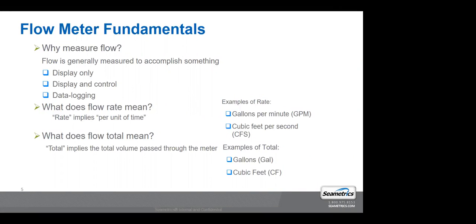Why do we measure it? We're accomplishing something. Either, like I just touched on, the totalized information, we're either displaying that data and we need to control something, control the pump, control something at that site, or we're data logging. How much water are we flowing through a given period of time? Flow rate implies a unit of time, and then the total implies the total volume passed through the meter. So normally if you're looking at a flow meter, you've got rate and total on it.